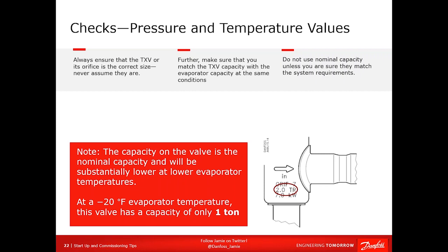If you're going to jam this thing in an ice cream freezer and you expect that 1 ton TXV to be 1 ton unit cooler that gives you 12,000 BTUs an hour at minus 20, because at minus 20, the TXV will give you, if you're lucky, half the nominal capacity it's rated for. So you'll only get 6,000 BTUs out of it. In the case of the example here, that number 7 orifice is going to give you 1 ton, half of what it's rated for at minus 20.